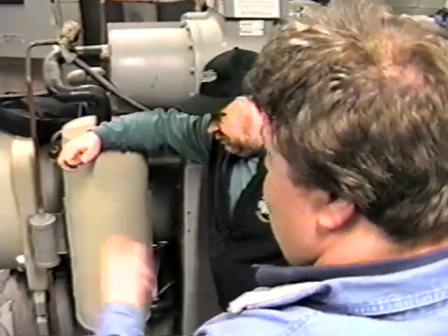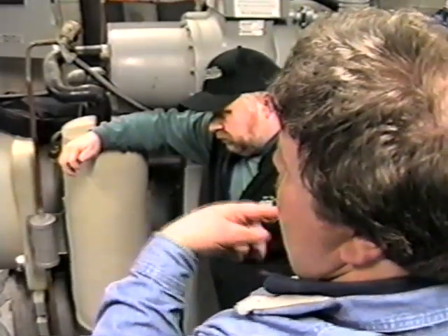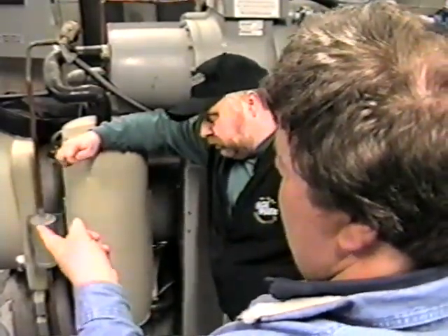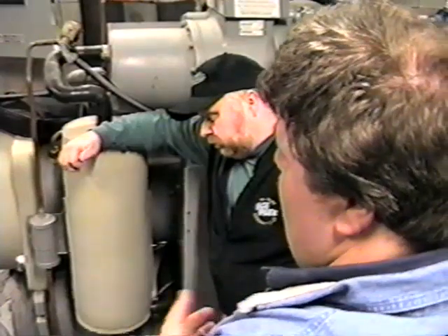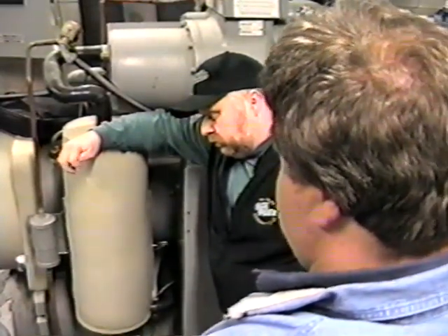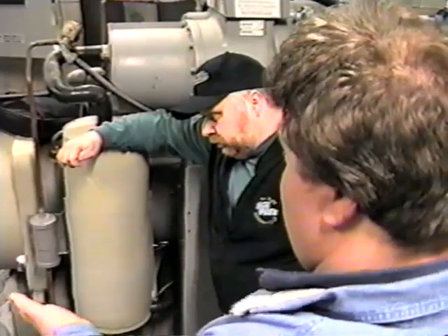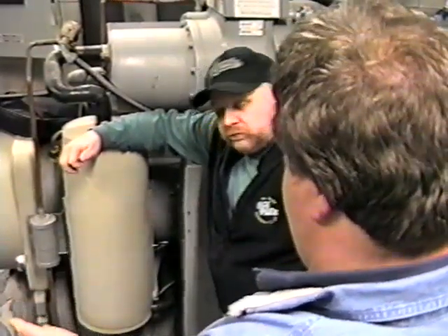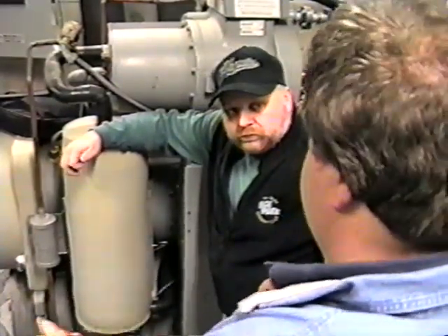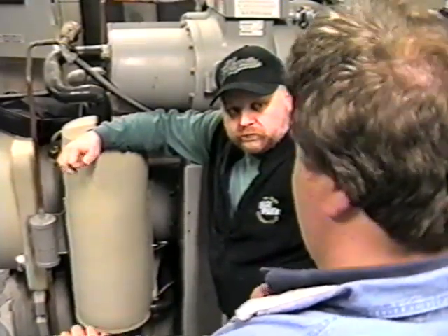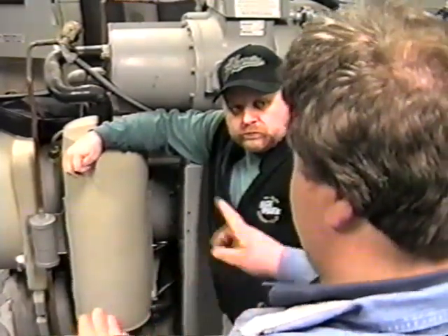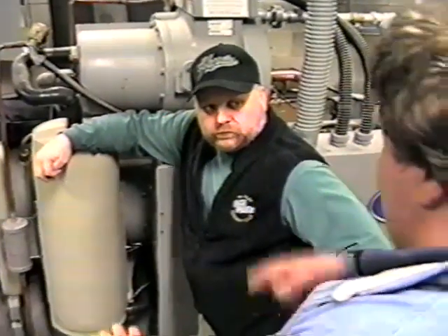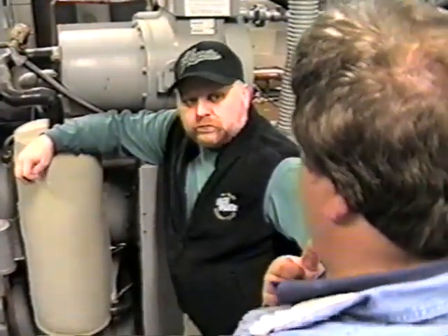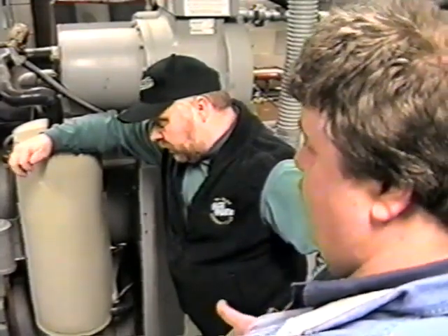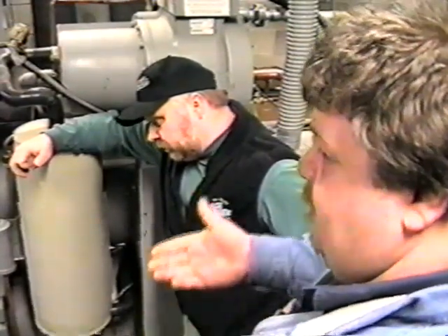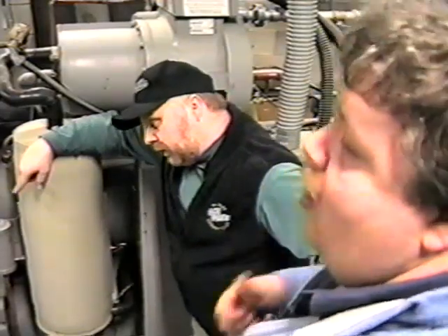So in here, number one, you've got the variable speed drive on the fan. The chiller's going to sequence up and try to maintain that water temperature. And we also have a bypass valve on the sump. So if we see that it's still extremely cold water, we bypass the water from the condenser and back right into the sump instead of letting it go to the tower. Right? The warmer the water gets, the valve will start opening slowly and finally eventually put all the water outside.